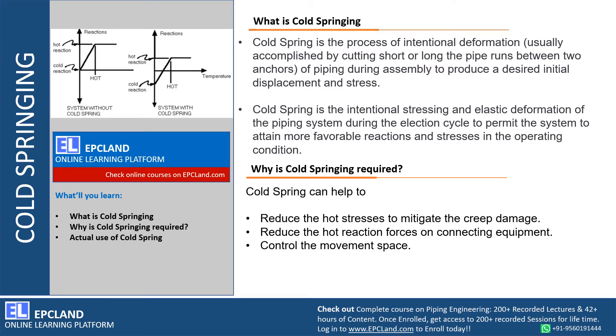So what we are doing is intentionally inducing the deformation with respect to displacement and stress. Indirectly, we can say cold springing is an intentional stressing and elastic deformation of a piping system during its erection cycle, to permit the system to attain favorable reaction. We want to have some stresses inside the system so that when there are reactions during operation, these can be utilized to reduce the negative impact.